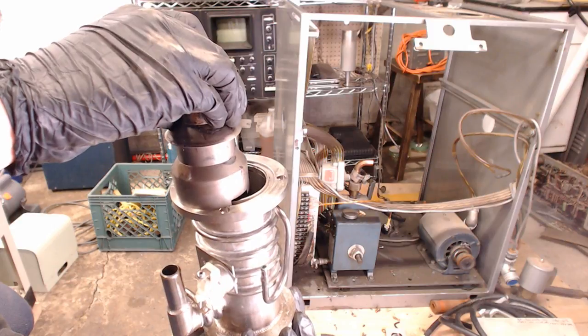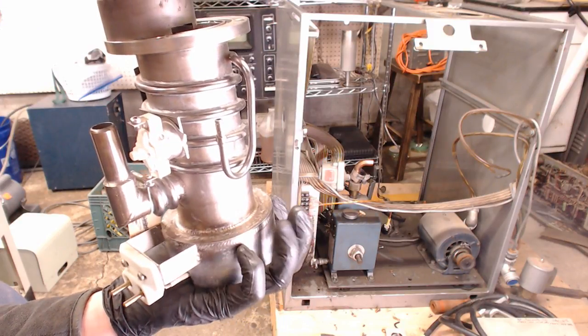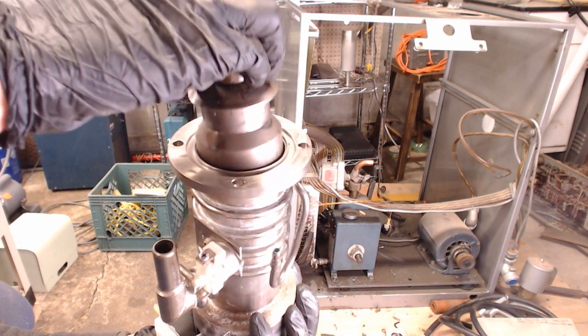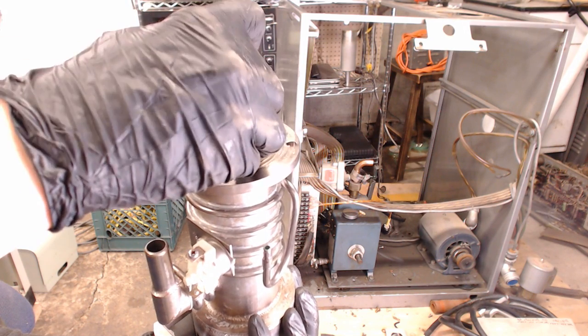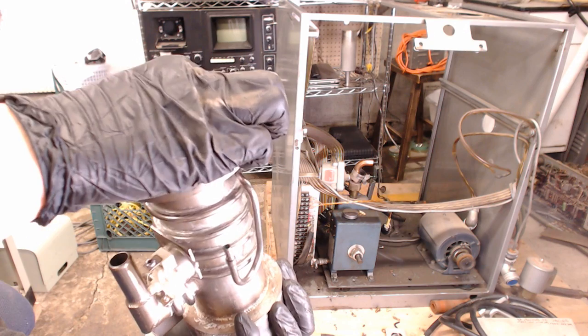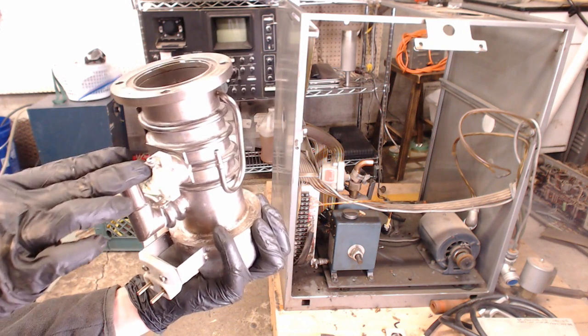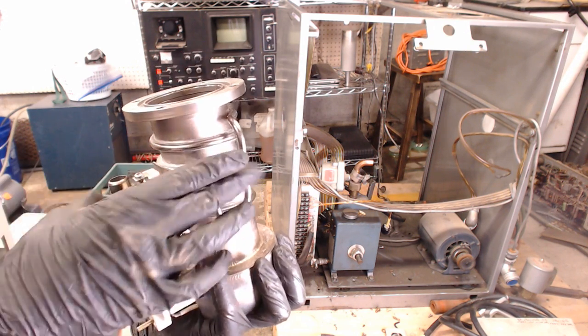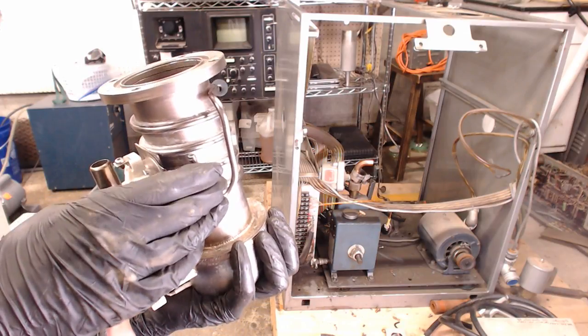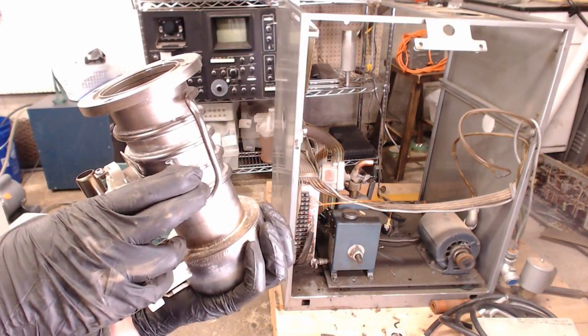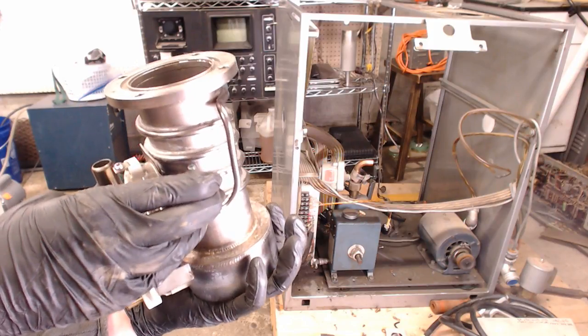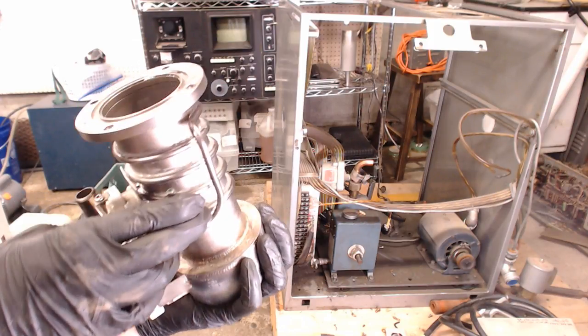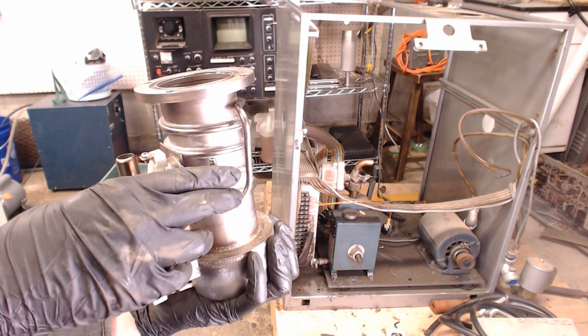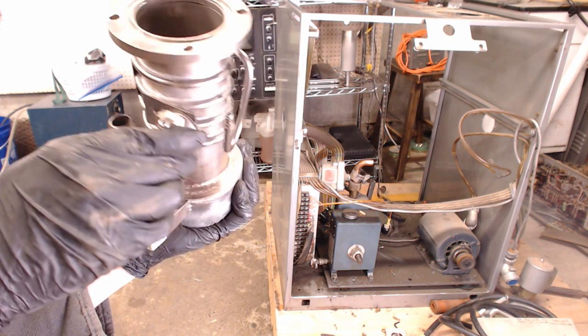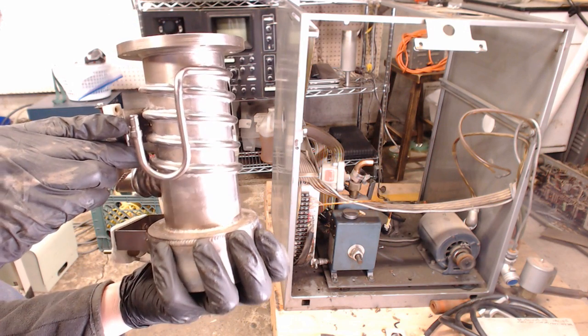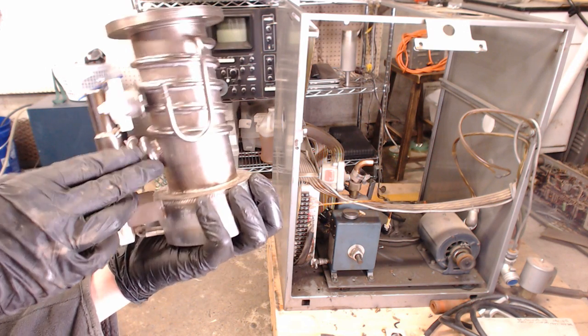And you've got to water cool the top part of that, because you only want the oil to be heated up on the bottom. You actually want the oil to condense once it hits the walls of this thing. So you've got to keep these water cooled. This is what the water chiller on my current SEM is for. All my water chiller does is keep the top part of this thing cold. On my new SEM, the JSM35C, the water chiller actually cools some of the electronics in addition to keeping the diffusion pump like this cold. And the diffusion pump on my new SEM is about twice the size of this diffusion pump, just to give you an idea. So it'll pump down a lot faster.